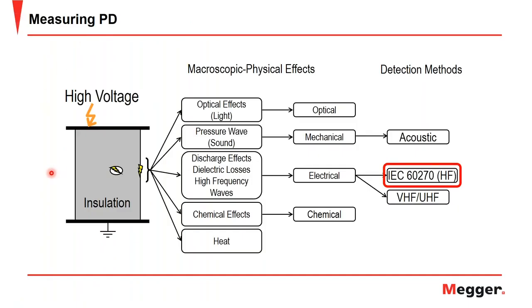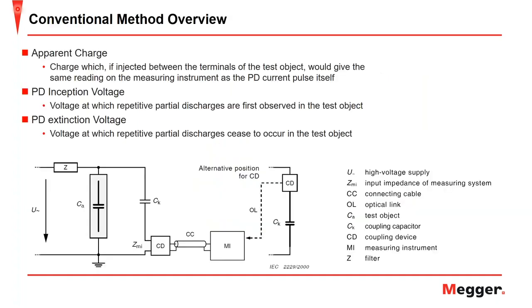Here we just have a visual overview of what was already stated. You have your insulation or your apparatus, high voltage being applied, and your partial discharge activity that emits many different things we can measure, such as optical effects, pressure waves, electrical effects like dielectric losses or high frequency waves, chemical effects, and heat. But right now we're going to focus on the electrical method. And of the electrical method, we will focus on the IEC 60270 or the conventional measurement method. Okay, so here we have the conventional method overview, and here we have the typical measurement circuit for the conventional method covered under the IEC 60270, and some important terms.